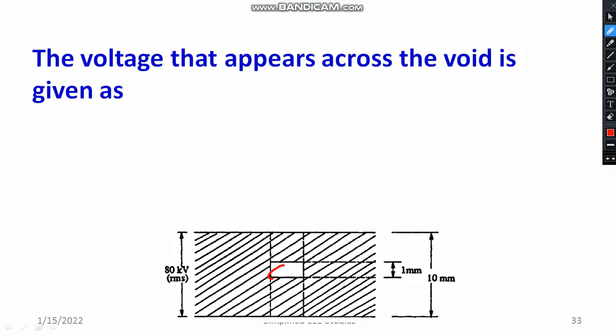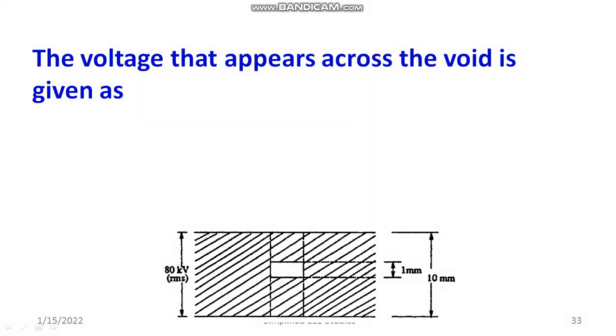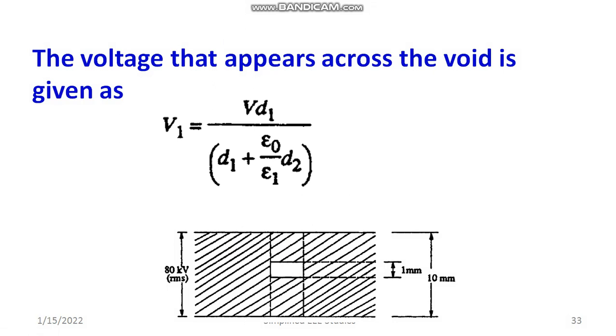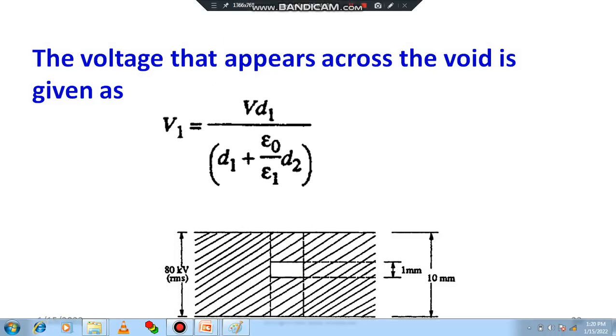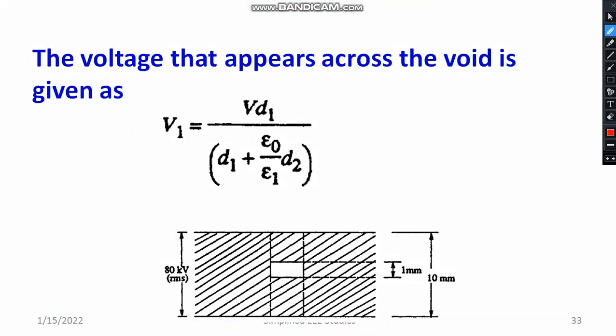Consider the void inside the dielectric medium, which is your solid dielectric material. The formula for voltage that appears across the void is: V1 = V·D1 divided by (D1 + (ε0/ε1)·D2), where D1 is the thickness of the void and D2 is the thickness of the solid dielectric material.